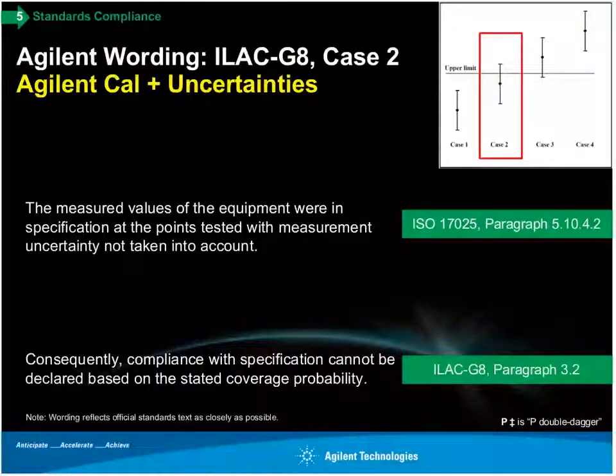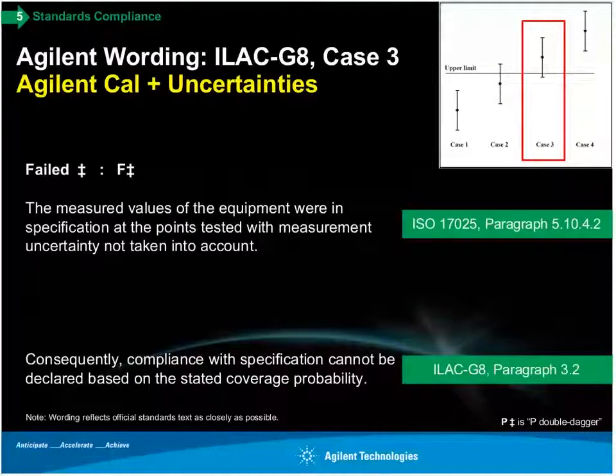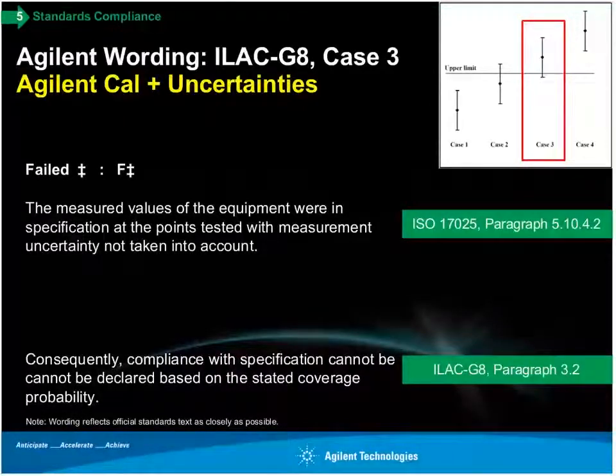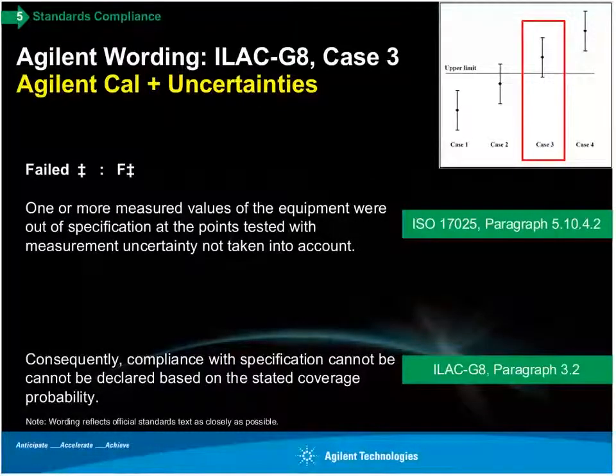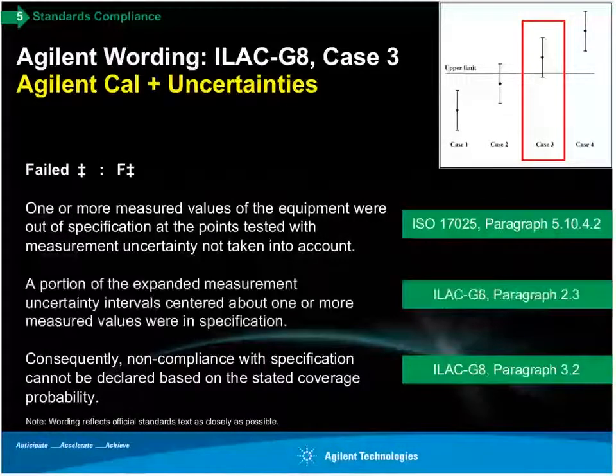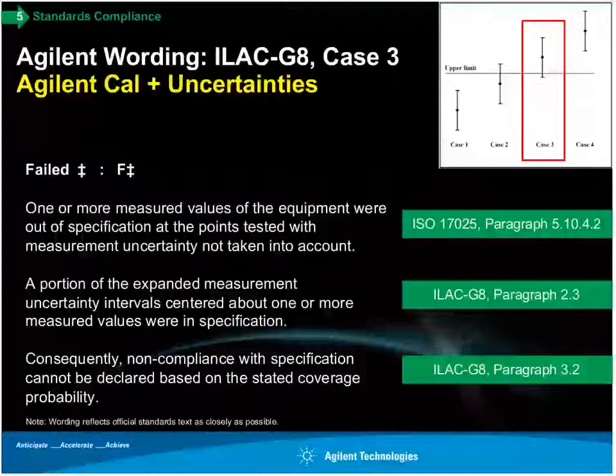Now I'm going to show you the next one, which is probably fairly obvious. If you measure a point that's outside the specification, but a portion of the uncertainty interval is inside, then officially we mark that as a fail, but because some portion of the measurement uncertainty is inside, we then designate it with a double dagger. We've just recently switched over to this. This is a new standard within Agilent, so if you look at our measurement reports right now, you won't see this just yet. But I'm letting you know because it's work that we're also circulating within the standards committees. We're hoping that other calibration labs will consider adopting this so that it's easier for all of you to interpret the results that you get from any calibration laboratory you might deal with.